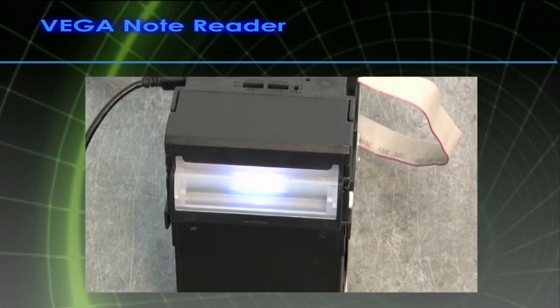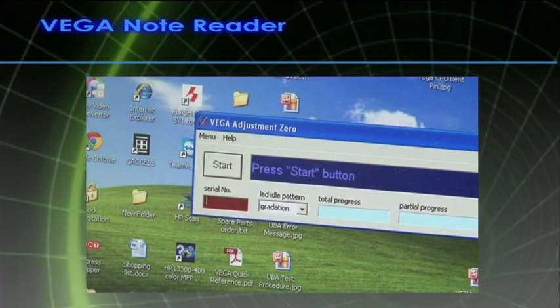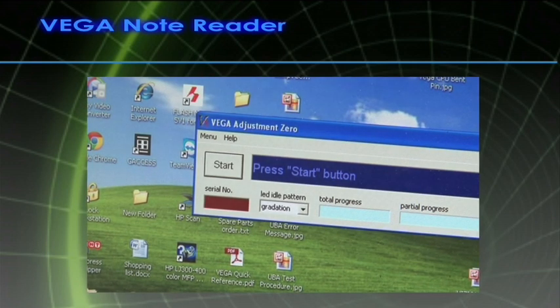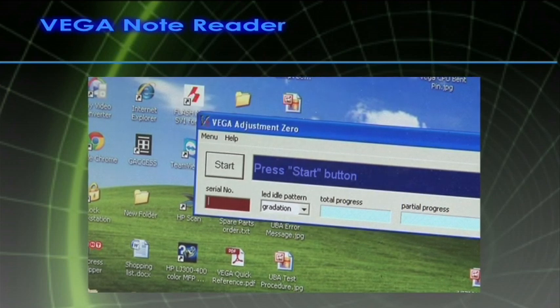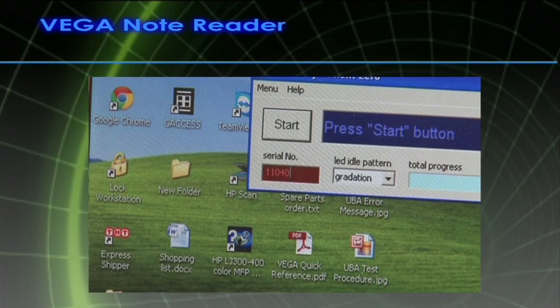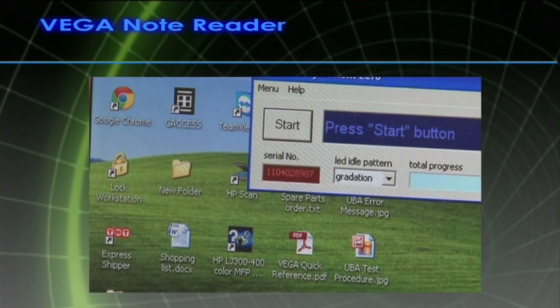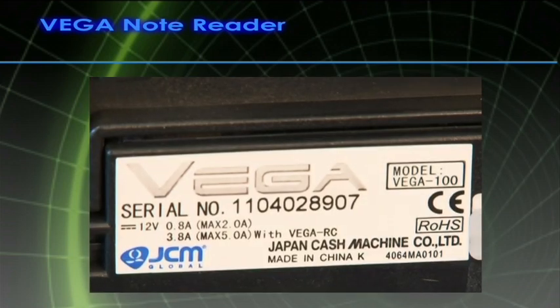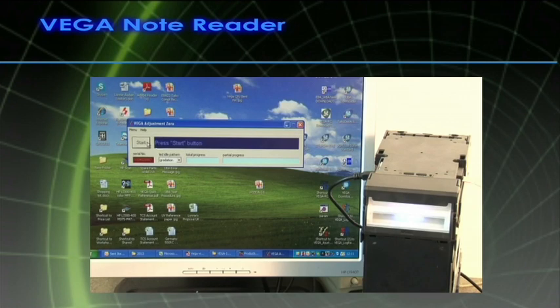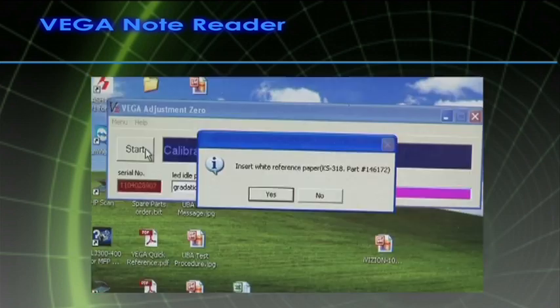Launch the Vega Adjustment Zero calibration program. Click on serial number, which is located just below the Start screen button. Type in the new Vega serial numbers. That's the 10-digit numbers which you can see at both sides of the Vega unit. Click on the Start screen button to begin the entrance sensors adjustment.